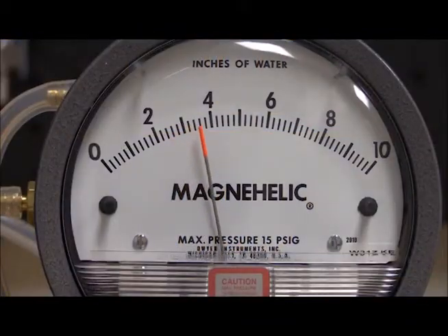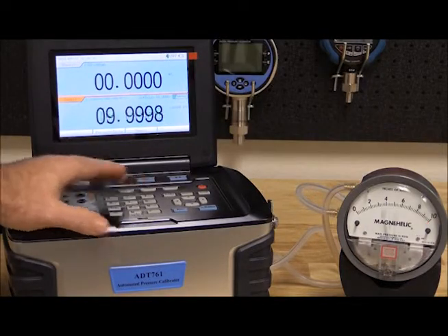To exercise the gauge, simply enter the full scale pressure and press enter. The 761 will supply pressure through a built-in pump and control to the full scale. To decrease the pressure, simply press vent.